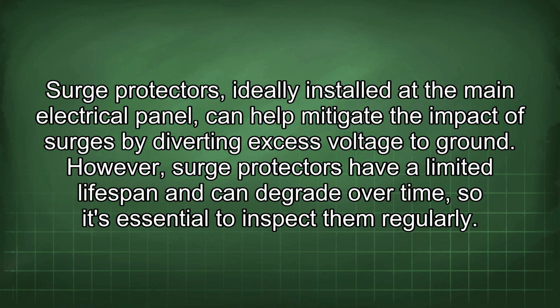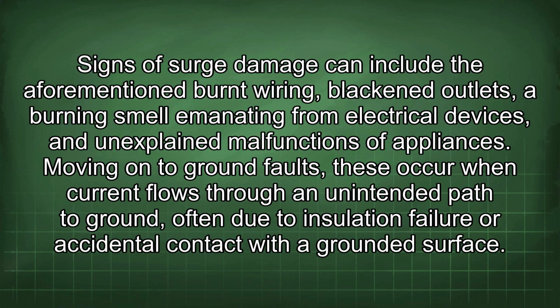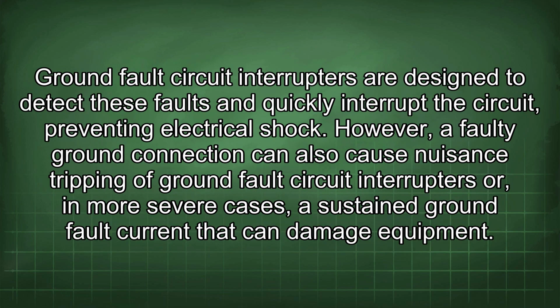excess voltage to ground. However, surge protectors have a limited lifespan and can degrade over time, so it's essential to inspect them regularly. Signs of surge damage can include the aforementioned burnt wiring, blackened outlets, a burning smell emanating from electrical devices, and unexplained malfunctions of appliances. Moving on to ground faults, these occur when current flows through an unintended path to ground, often due to insulation failure or accidental contact with a grounded surface. Ground fault circuit interrupters are designed to detect these faults and quickly interrupt the circuit, preventing electrical shock. However, a faulty ground connection can also cause nuisance tripping of ground fault circuit interrupters or, in more severe cases, a sustained ground fault current that can damage equipment.